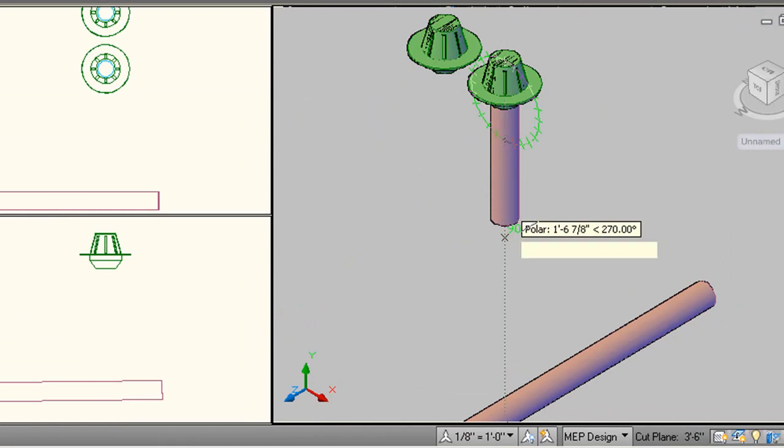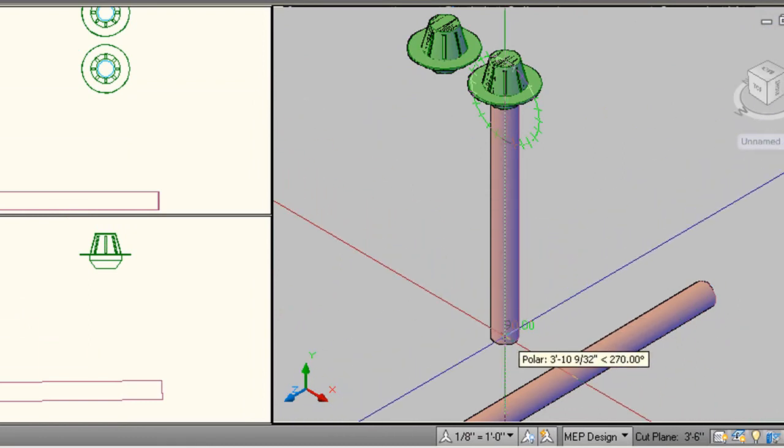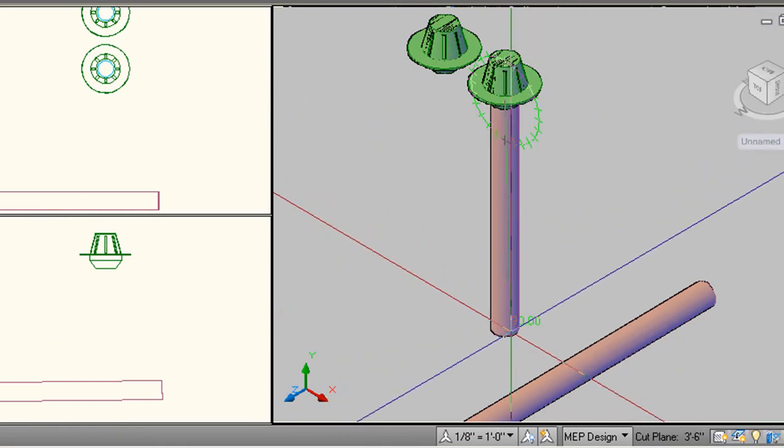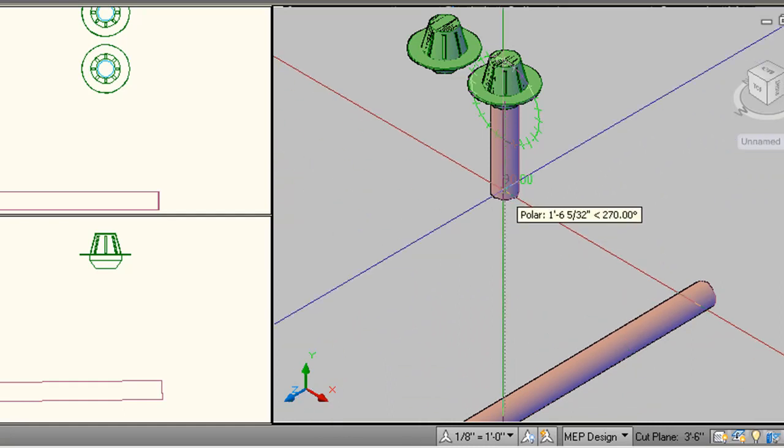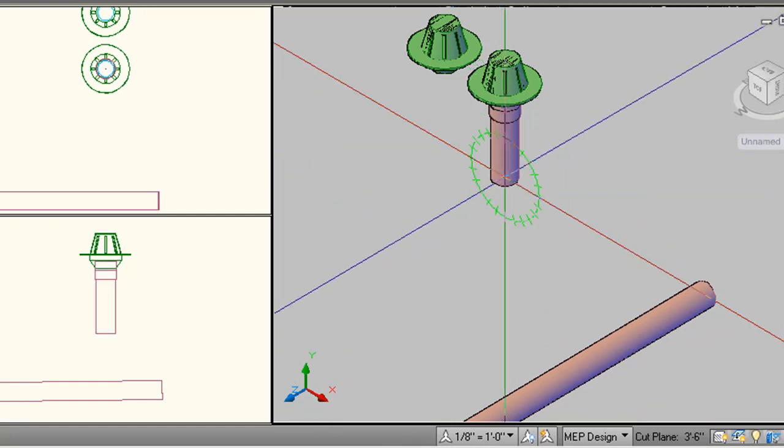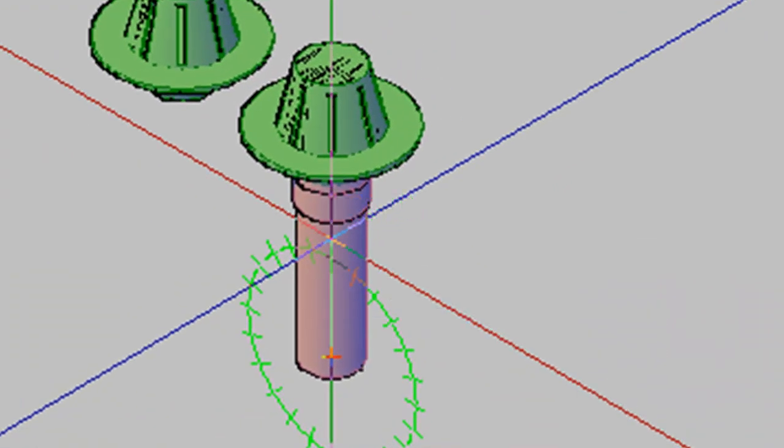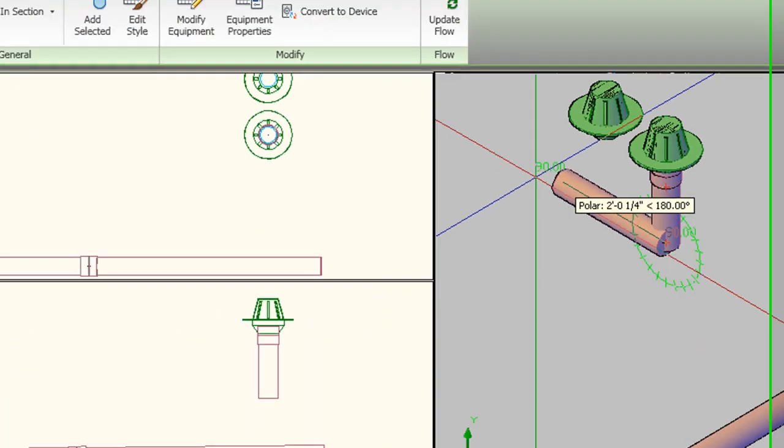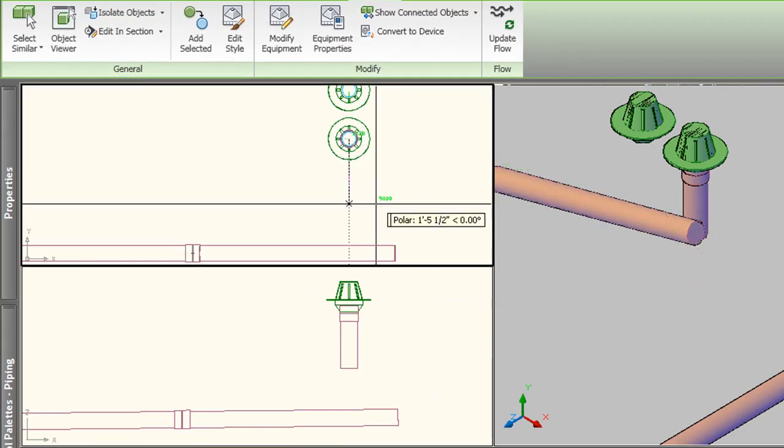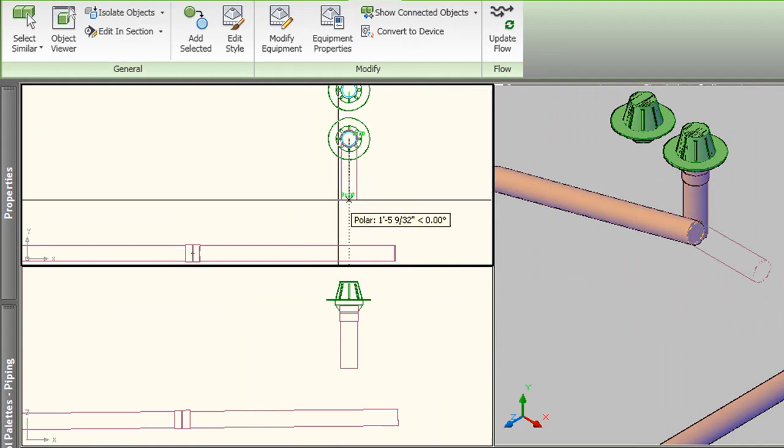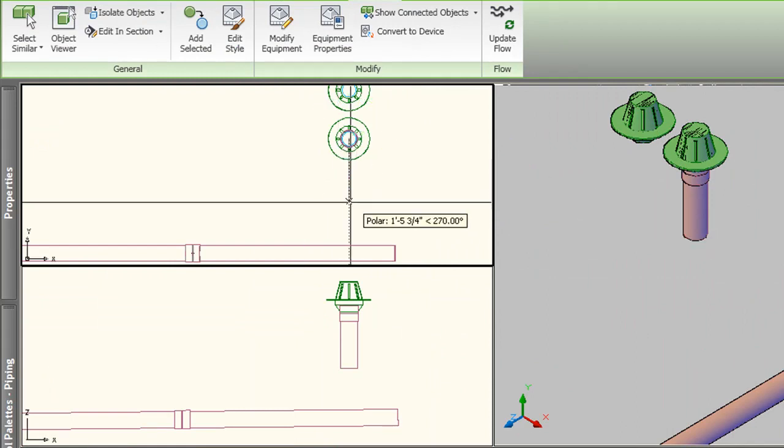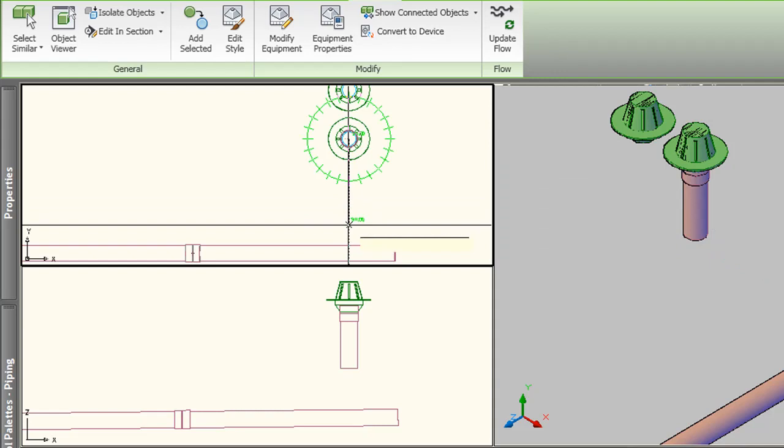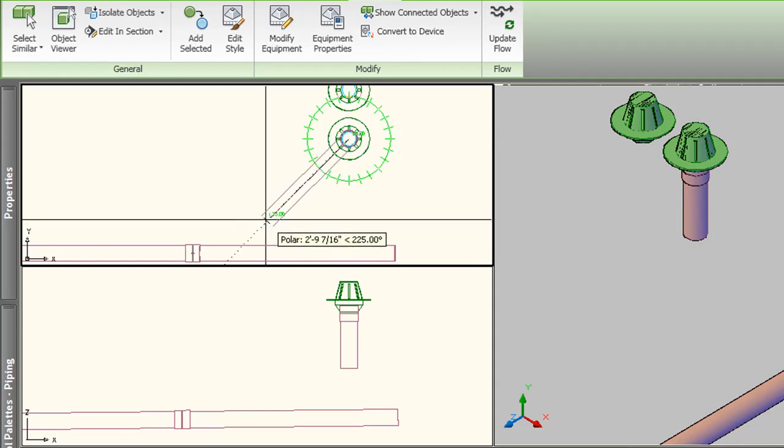So now I want to drop this riser. I just don't want to go below the height of the branch or else my ladder will have to come back up to meet that branch. But it's fine to stay above it. So let's come down a foot or a foot and a half. And notice that AutoCAD MEP has added my fittings for me, which is nice. I can come over here to my plan view. And again, I'm stuck. I can't move. So let's use the plane command. There's my compass rose. And I can finish off by connecting it in a 90 for a T or to 45 with a Y.